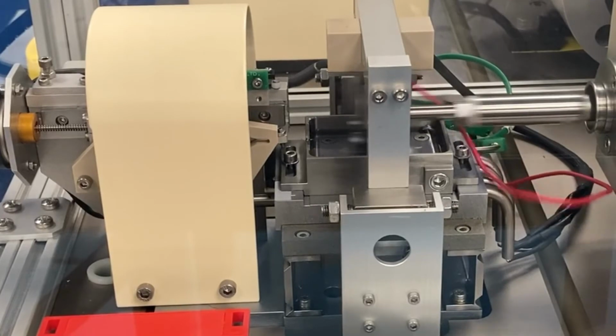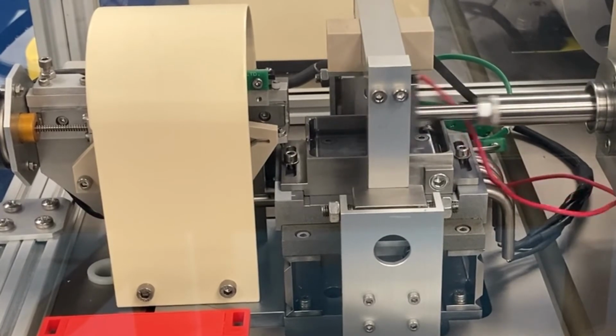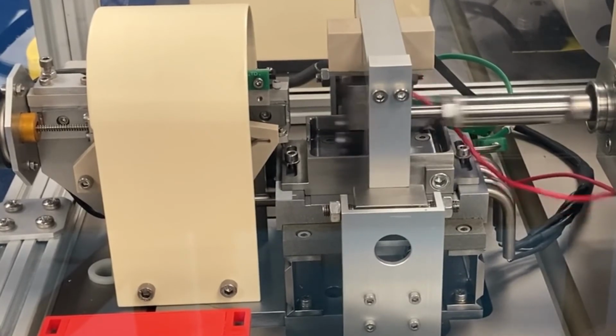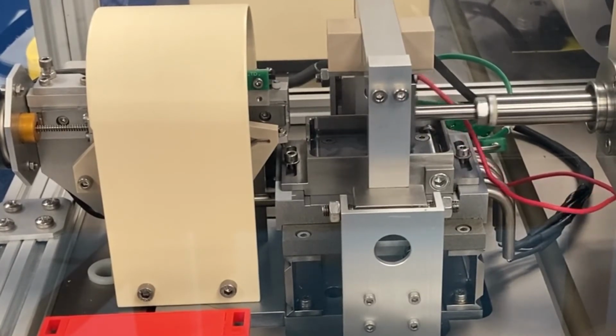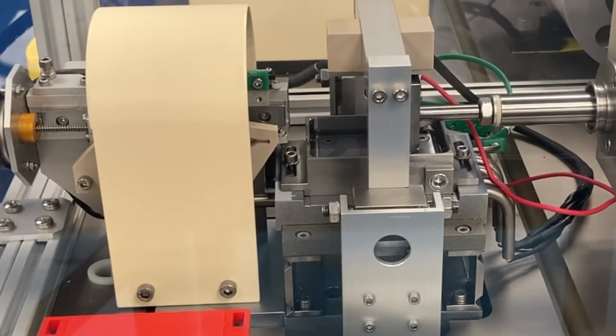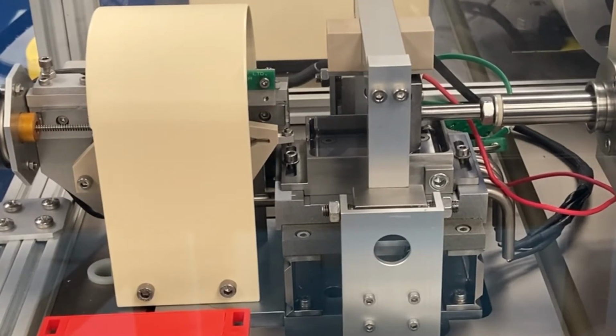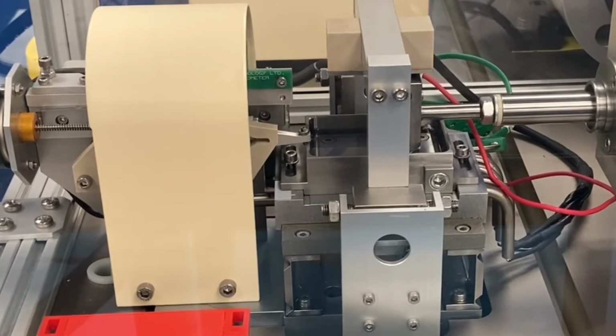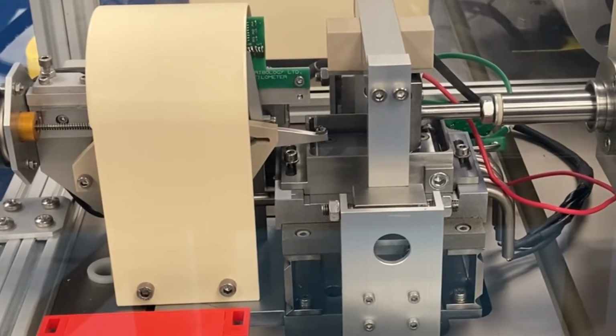The device uses in situ tactile profilometry for periodic measurement of the developing wear scar. The probe is indexed along the wear scar, then onto the unworn part of the specimen from just past the mid-stroke position, so that just over half the wear scar is sampled. Every time a measurement is programmed, the reciprocating specimen head is automatically withdrawn to the stroke end furthest from the profilometer.